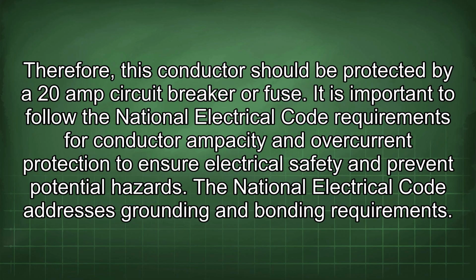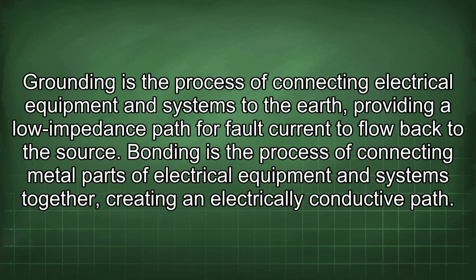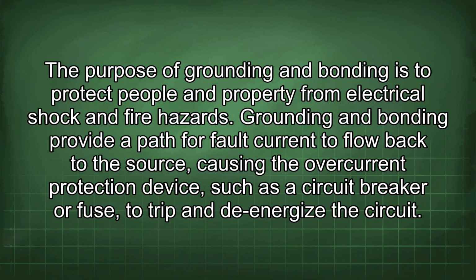and prevent potential hazards. The National Electrical Code addresses grounding and bonding requirements. Grounding is the process of connecting electrical equipment and systems to the earth, providing a low impedance path for fault current to flow back to the source. Bonding is the process of connecting metal parts of electrical equipment and systems together, creating an electrically conductive path. The purpose of grounding and bonding is to protect people and property from electrical shock and fire hazards. Grounding and bonding provide a path for fault current to flow back to the source, causing the overcurrent protection device, such as a circuit breaker or fuse, to trip and de-energize the circuit.